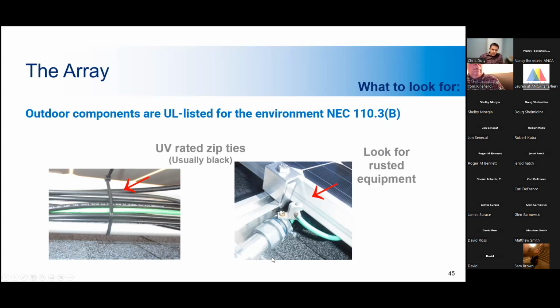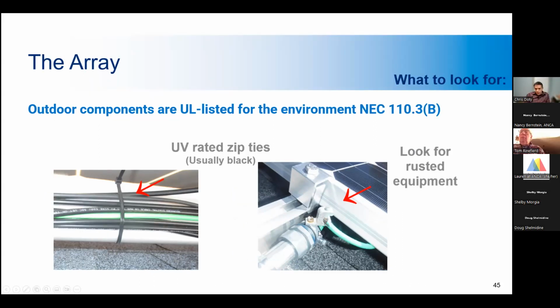On the right, you can see another use of non-weather rated equipment. It's kind of hard to see, but here you can see this screw that's used to hold the ground lug onto the conduit. It's rusting, which means it's not outdoor rated, and probably within a couple of years it'll just rust away, and that ground lug will probably just be hanging there, not connected to the conduit.